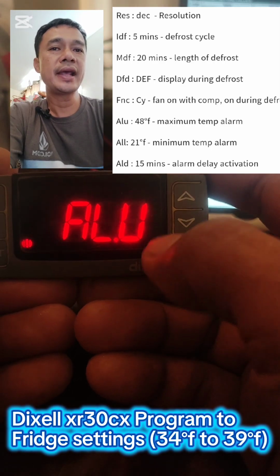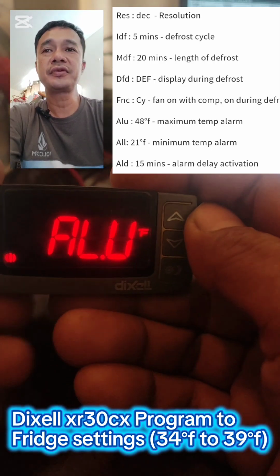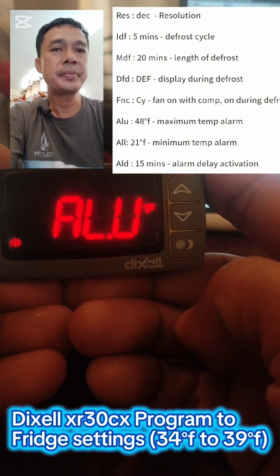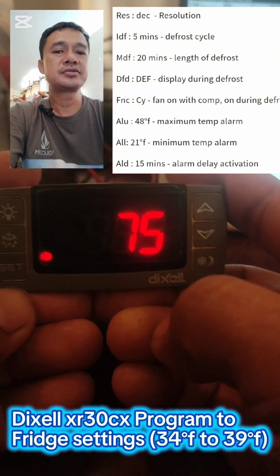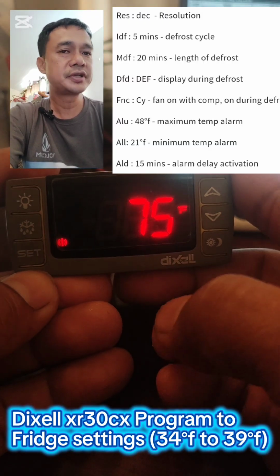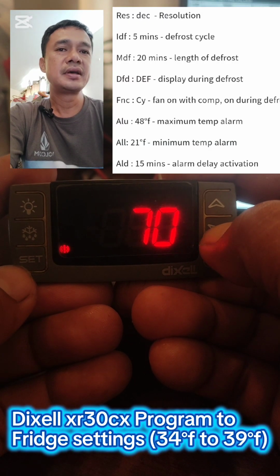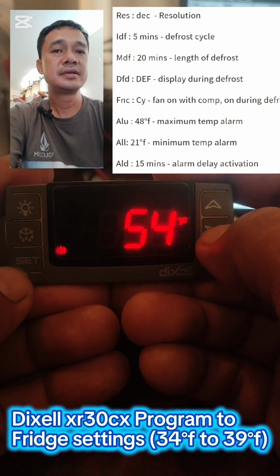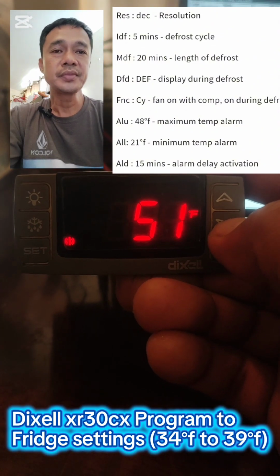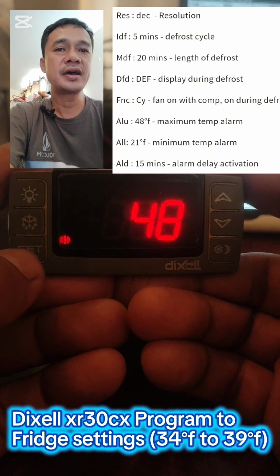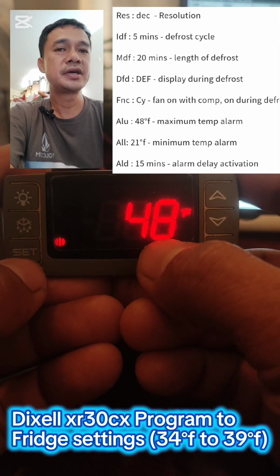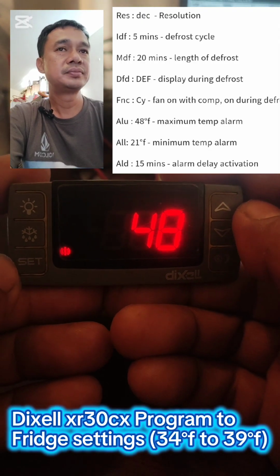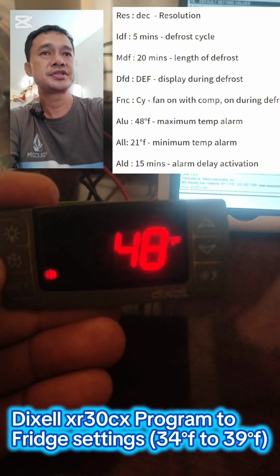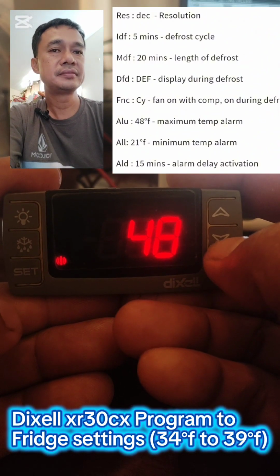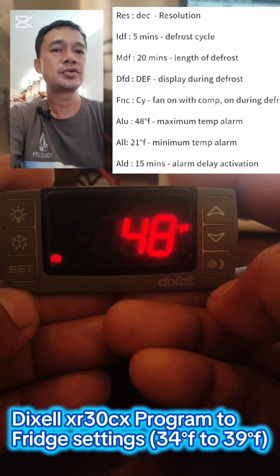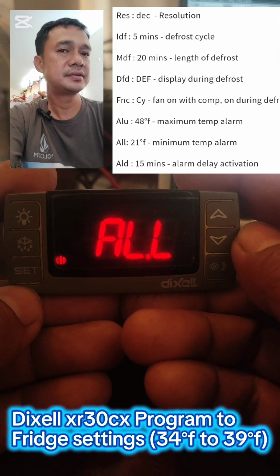Let's go to ALU, and this ALU stands for maximum temperature alarm, and it's set to 75 because they use this for the condensing unit. And I'm going to set it to 48 degrees Fahrenheit, since my maximum set point is set to 38. Press set to memorize. I just add it.